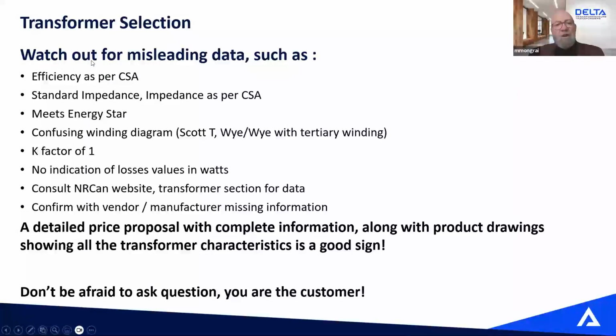And please watch out for all those misleading data on drawings and quotes, when it says efficiency as per CSA, standard impedance, meets Energy Star. Confusing wiring diagram. Don't use T-connected transformers on renewable. K factor of 1. A K factor is the ratio of losses under no harmonic and harmonic conditions. So a ratio of 1 means there's no K rating. You have a standard transformer.